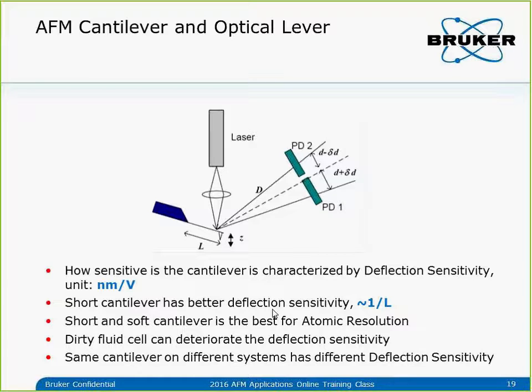A cantilever with high deflection sensitivity can measure smaller bending, meaning better force control. Another factor is the spring constant — a soft cantilever with smaller spring constant means better force control. So the best combination for atomic resolution imaging is a short cantilever with small spring constant — short and soft is best.